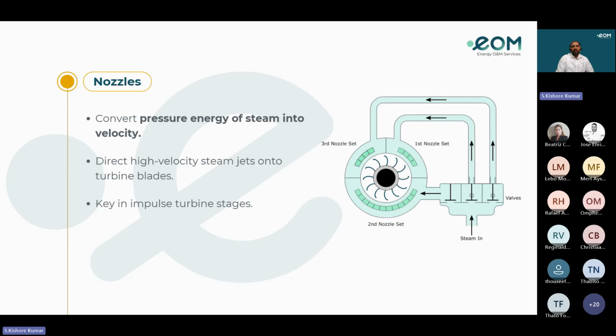Nozzles. Coming to the nozzles, they convert the pressure energy of steam into velocity. They direct high velocity steam jets onto turbine blades and are key in impulse turbine stages. It is recommended to always check the wheel chamber pressure during startup, and how much pressure is needed to start or spin the turbine into rotation. If the pressure draw is higher, it means there is possible damage or aging of the system. So always be vigilant about how much pressure is needed in the wheel chamber to start or spin the turbine into rotation.